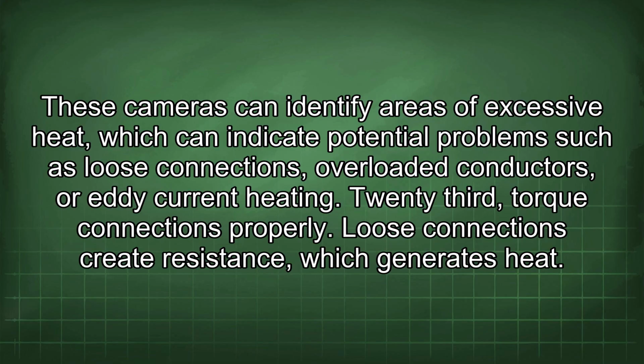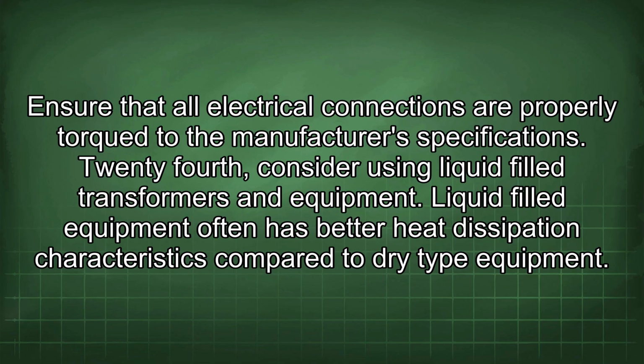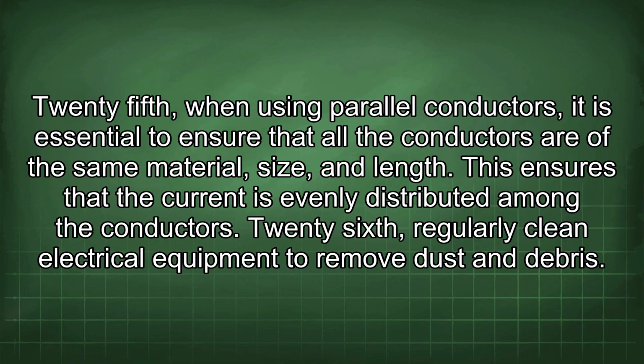Loose connections create resistance, which generates heat. Ensure that all electrical connections are properly torqued to the manufacturer's specifications. 24th, consider using liquid-filled transformers and equipment. Liquid-filled equipment often has better heat dissipation characteristics compared to dry-type equipment. 25th, when using parallel conductors, it is essential to ensure that all the conductors are of the same material, size, and length. This ensures that the current is evenly distributed among the conductors.